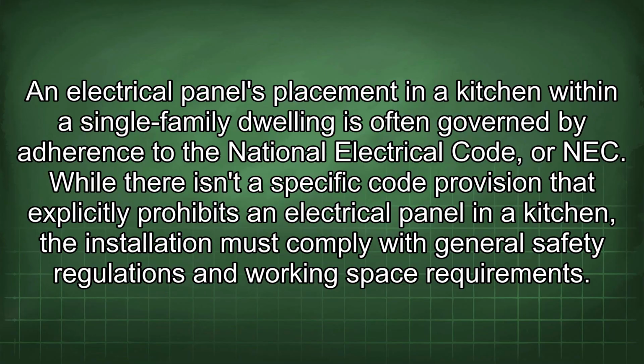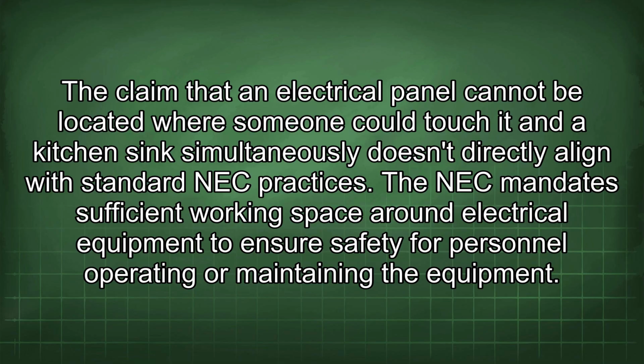An electrical panel's placement in a kitchen within a single-family dwelling is often governed by adherence to the National Electrical Code, or NEC. While there isn't a specific code provision that explicitly prohibits an electrical panel in a kitchen, the installation must comply with general safety regulations and working space requirements. The claim that an electrical panel cannot be located where someone could touch it and a kitchen sink simultaneously doesn't directly align with standard NEC practices.